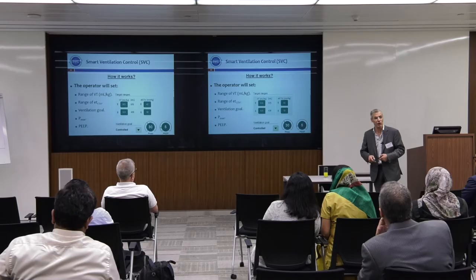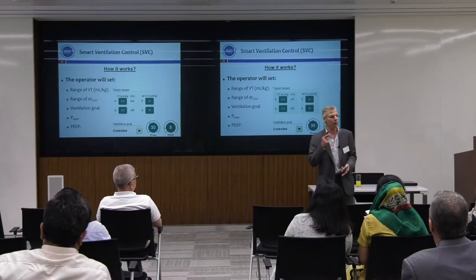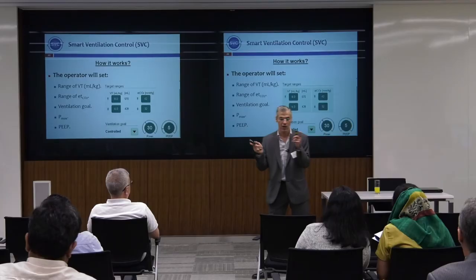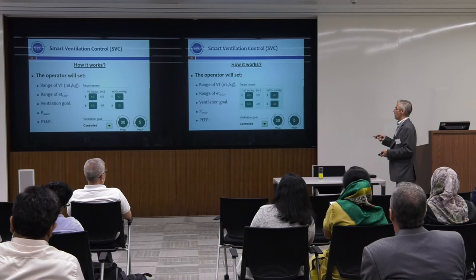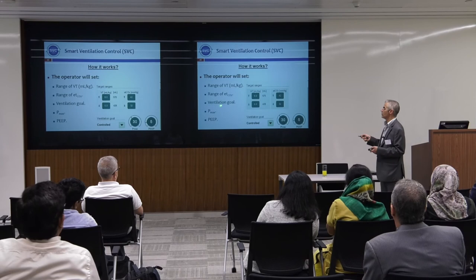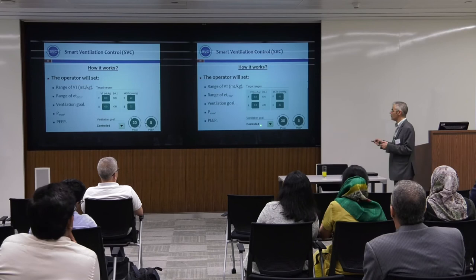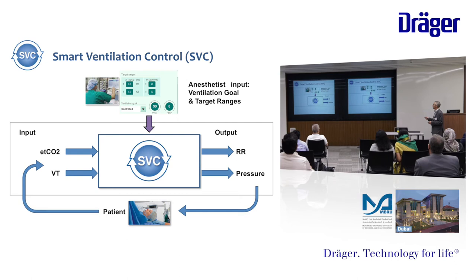We have four ventilation targets: I would like to suppress patient ventilation totally; I would like to augment the patient toward spontaneous breathing; I will just allow the patient to breathe spontaneously but not augment it; or I would like to go for extubation — I want the patient to be 100% spontaneous. This is what's called my target. Depending on the target, the machine gives me a default setting that I can change. I then set the ventilation goal — pressure max and PEEP — and tell the machine: please do the job. The machine sets respiratory rate, pressure support or pressure control, and adjusts based on tidal volume delivered to the patient. From the patient output, it gets tidal volume and end-tidal CO2 and keeps this cycle while I'm watching.